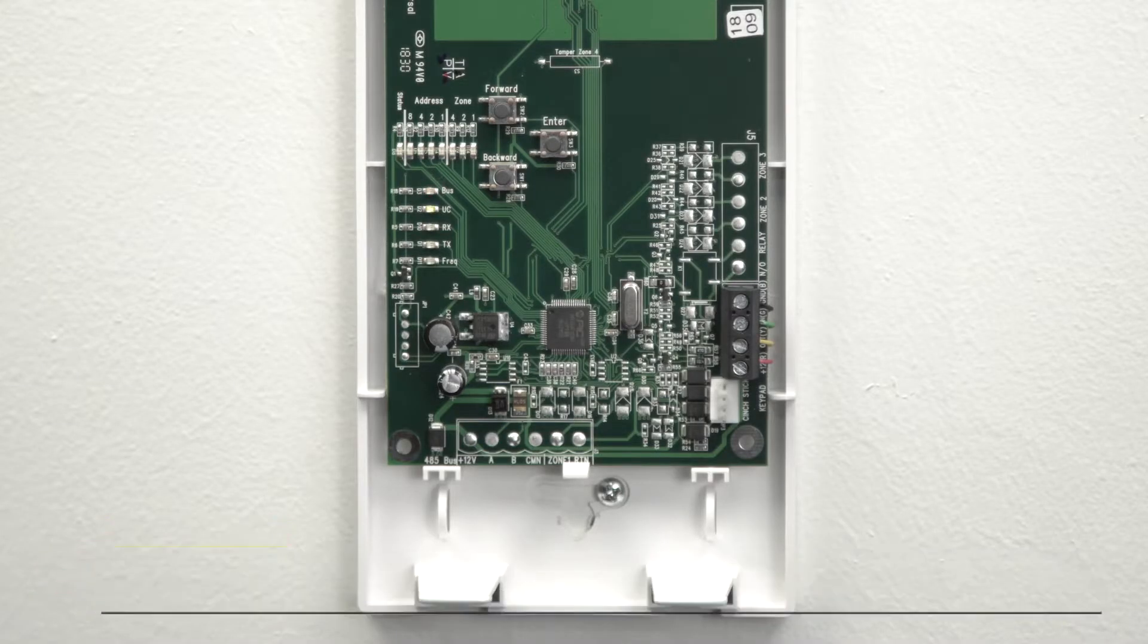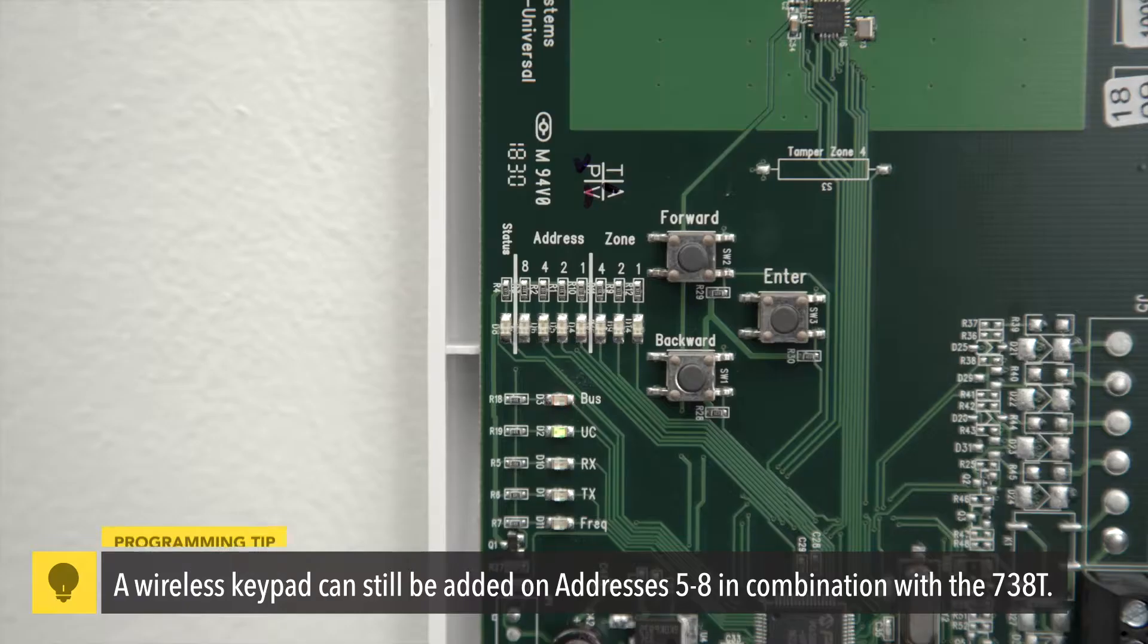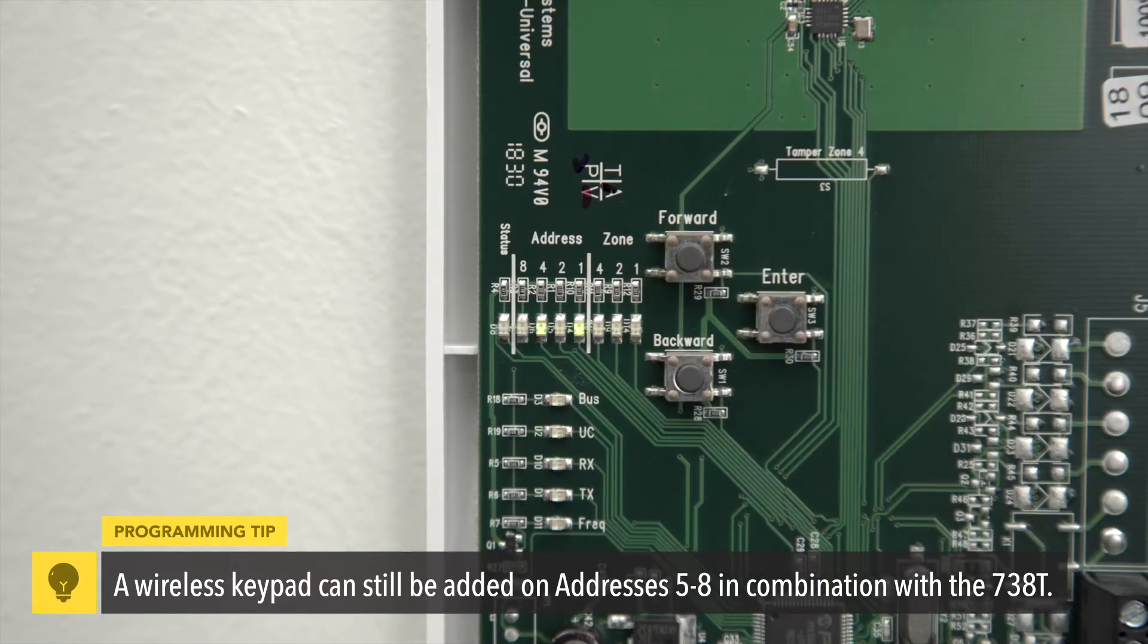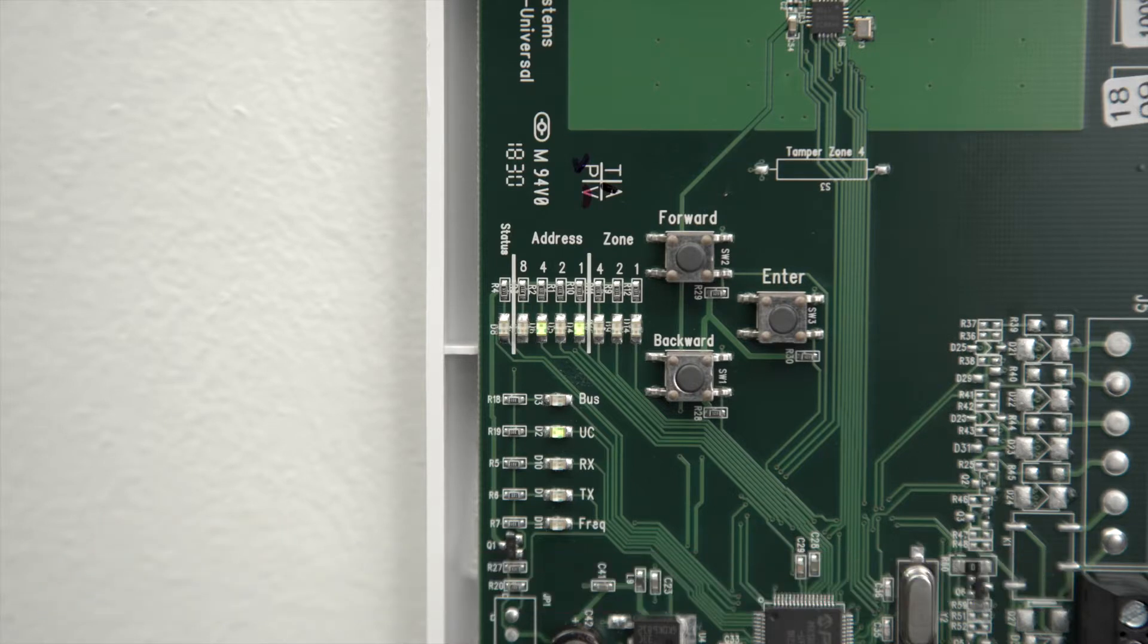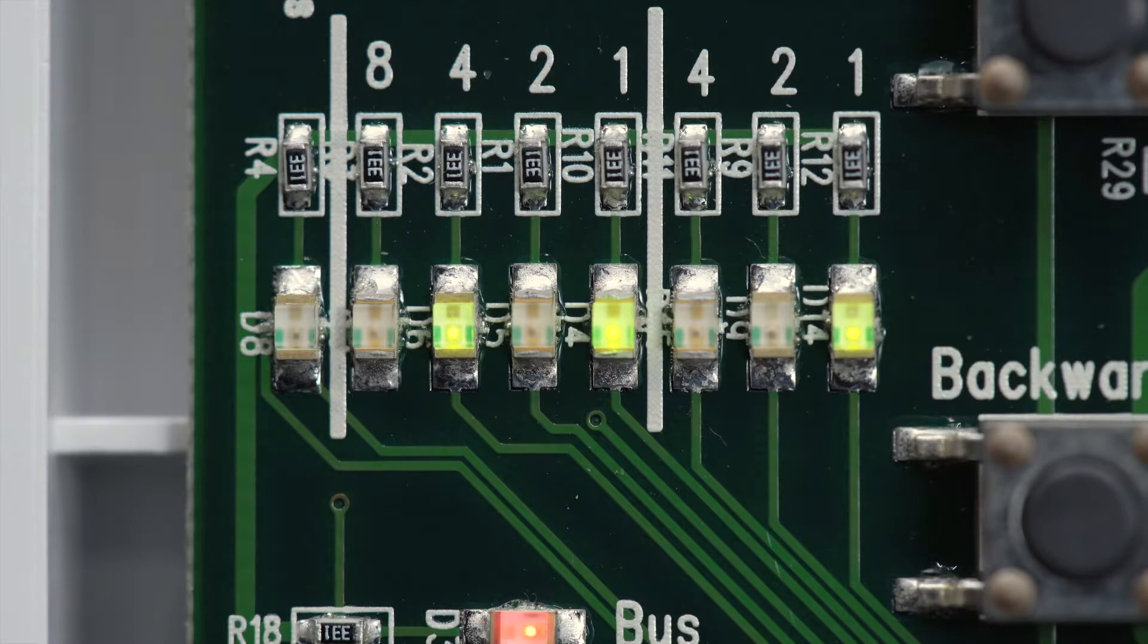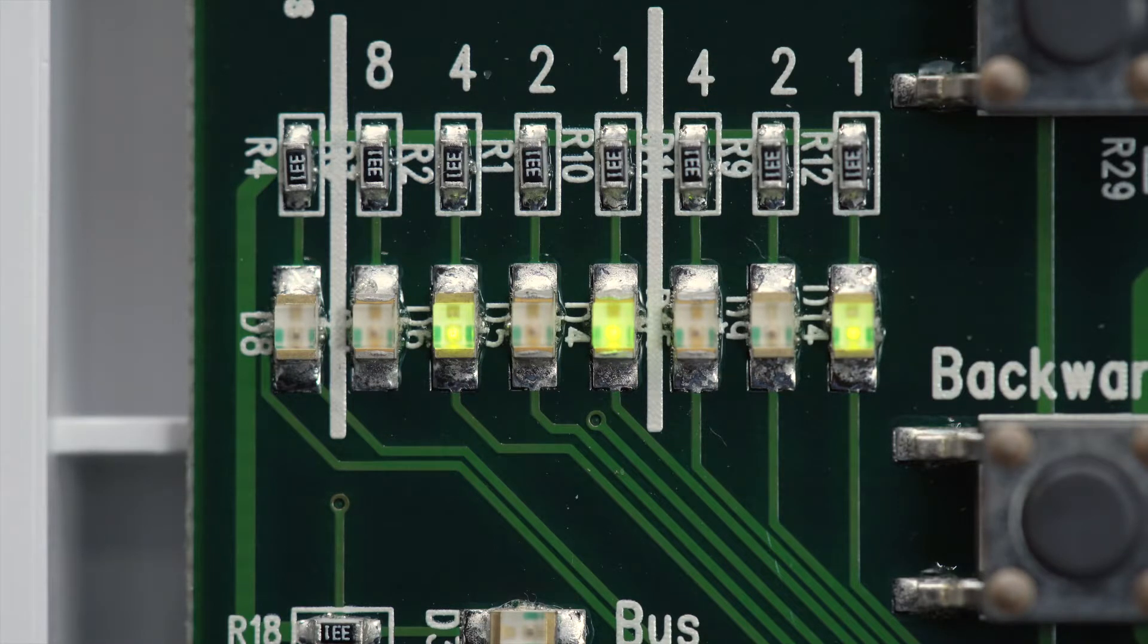Next, get the 738T ready to enroll transmitters by pressing the forward and back buttons at the same time. The address LED will light up, displaying an address. Add the numbers together to determine the address. For example, if the 1 and 4 LEDs light up, you have selected address 5.